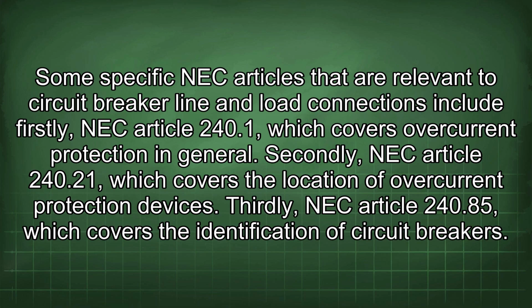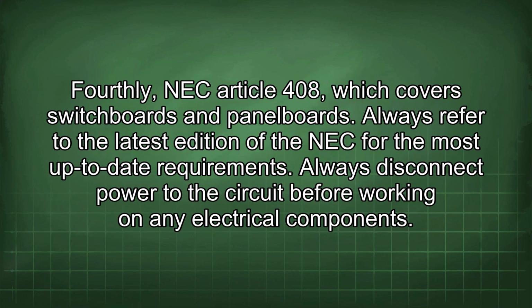Some specific NEC articles that are relevant to circuit breaker line and load connections include: firstly, NEC Article 240.1, which covers overcurrent protection in general. Secondly, NEC Article 240.21, which covers the location of overcurrent protection devices. Thirdly, NEC Article 240.85, which covers the identification of circuit breakers. Fourthly, NEC Article 408, which covers switchboards and panel boards. Always refer to the latest edition of the NEC for the most up-to-date requirements.